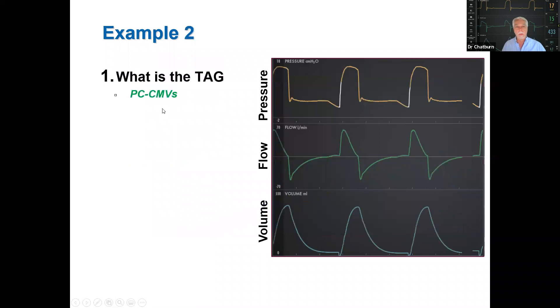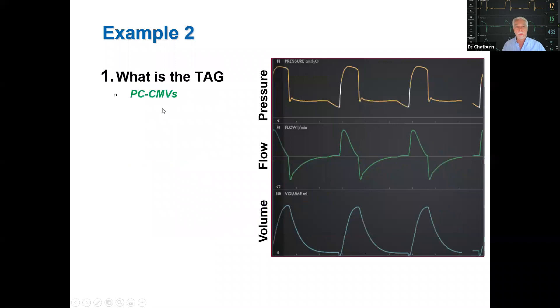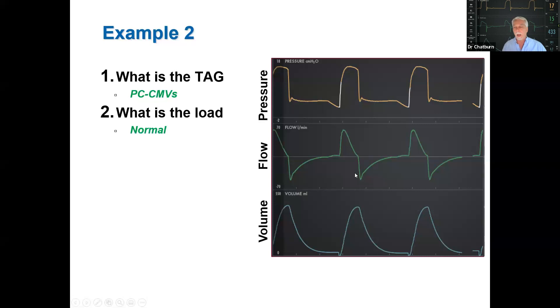Here's another example. The tag is again pressure control from the pressure, volume, and flow waveforms. The load appears normal — the expiratory time constant looks normal with a nice high peak expiratory flow and reasonable decay over a couple of seconds, no indication of high resistance or elastance.